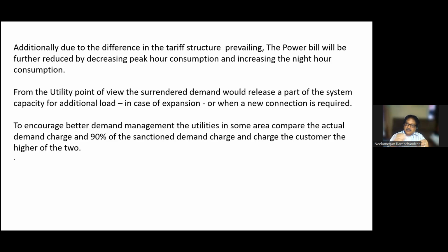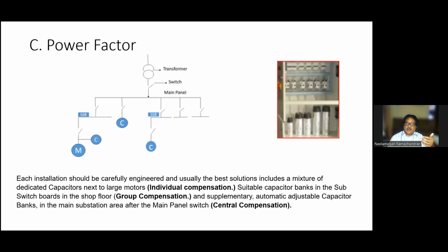So, carefully looking at our past records, I think the data will be there. By collecting the record data for so many years, we can see what the sanctioned demand is and what demand we are reaching continuously. So why can't we surrender the excess demand, so that the fixed charge in the EB bill comes down straight away? This is another example. Having said that about time of the day and maximum demand, now the power factor.